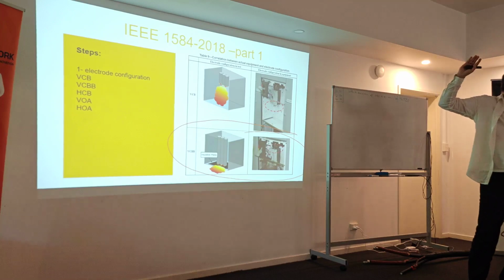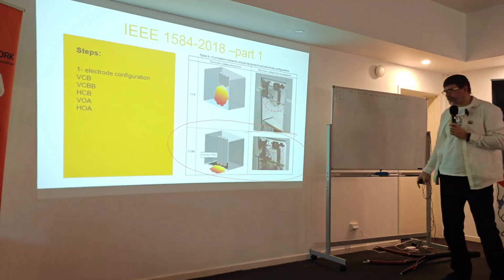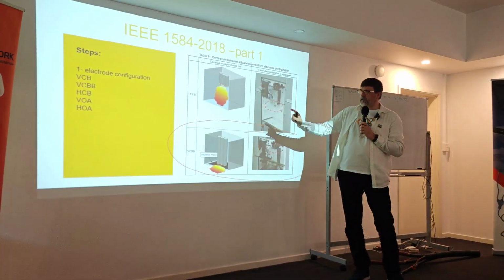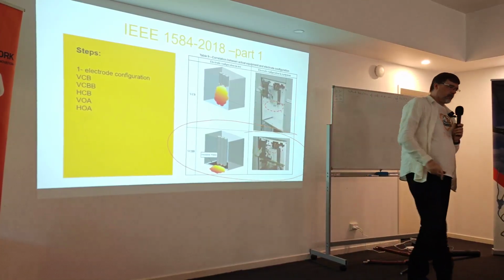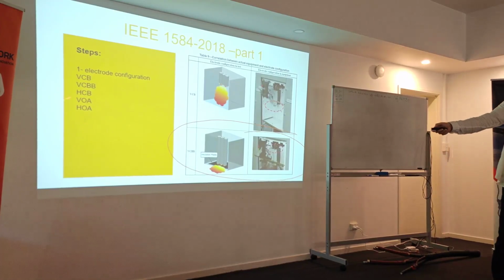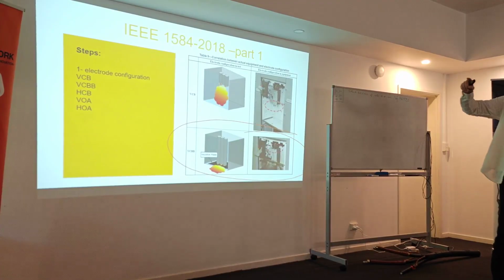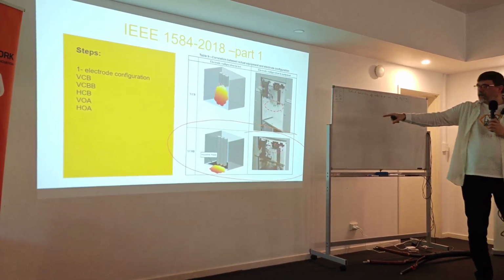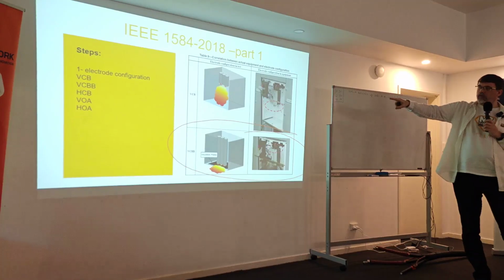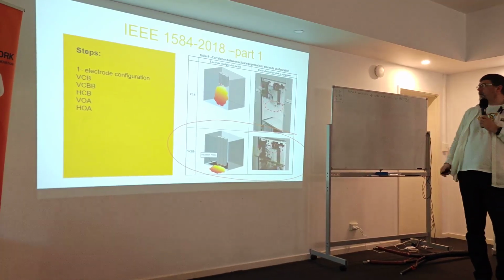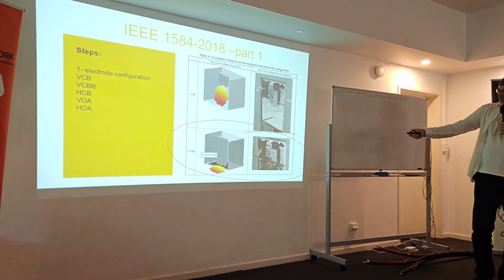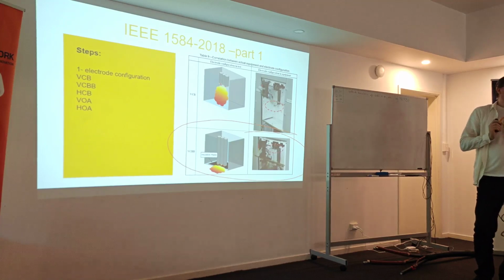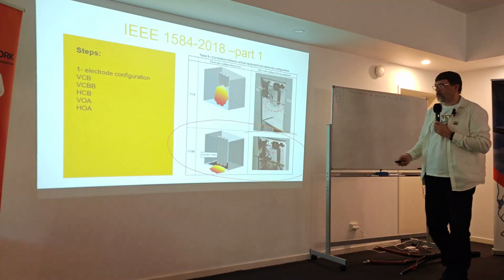First step, we have electrode configurations. That's something I have to explain. In IEEE, in the past it was 3, now it's 5. So we have something called VCB, VCBB, HCB, and VOA, HOA. If you translate it, it's vertical circuit breaker, vertical circuit breaker barrier, horizontal circuit breaker, horizontal open arc, and vertical open arc. So this is the reference point that they used. I can show you some example. Technically, in one panel you have multiple configurations in multiple places, so you try to choose the common one and the most likely one.